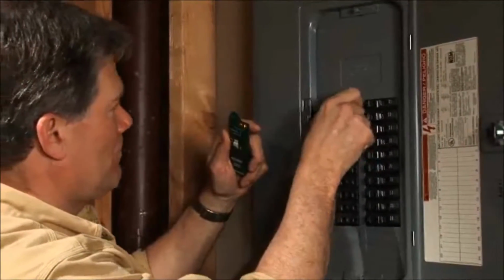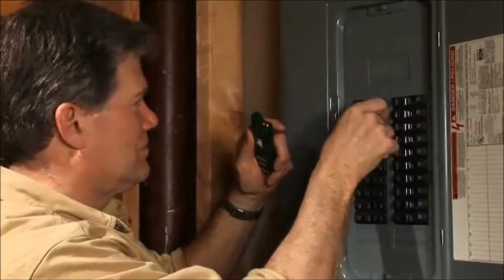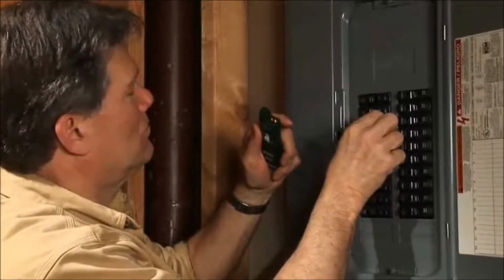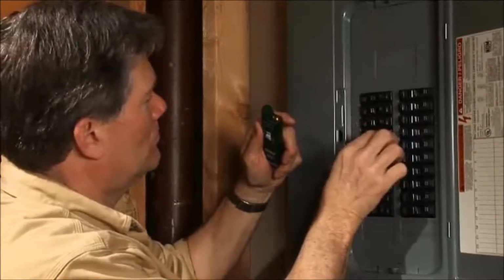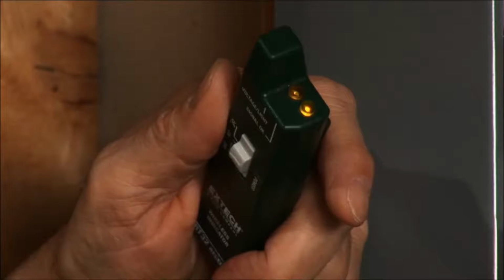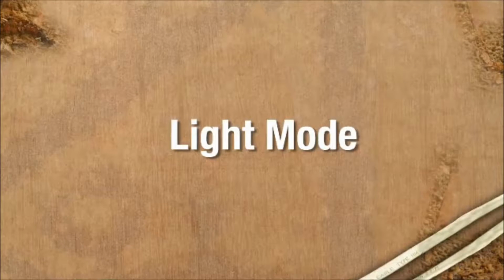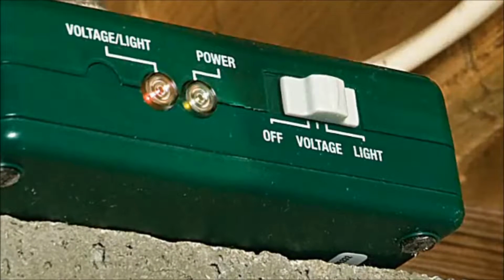Sequentially switch breakers on and off. Once power to the circuit or cable which the transmitter is clamped onto is interrupted, the tone alert will stop and the amber LED will go off, thereby identifying the cable. Light mode. Switch the transmitter unit to light mode.